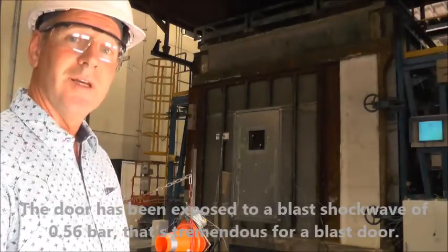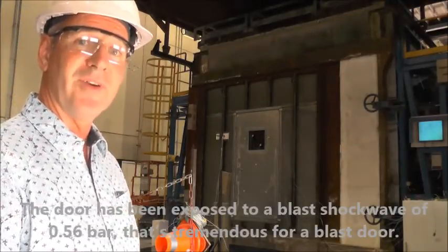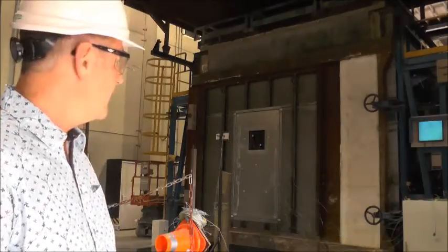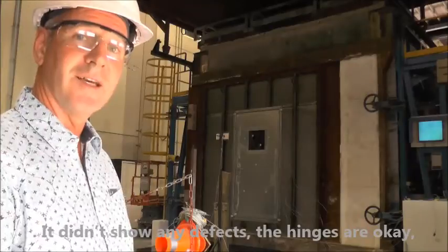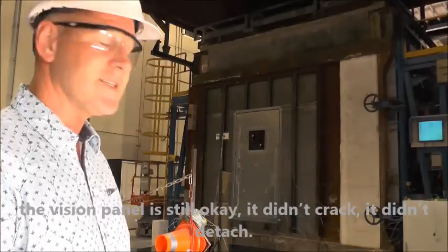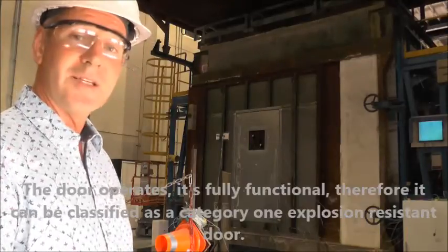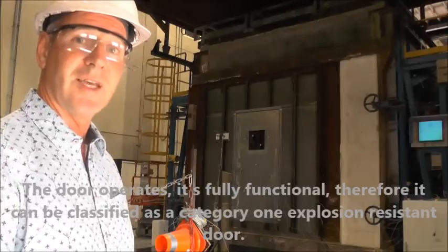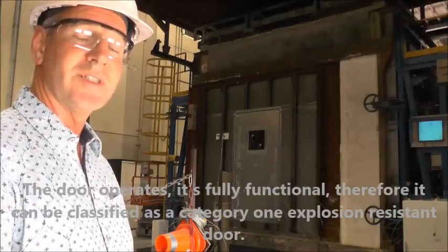The door was exposed to a blast shockwave of 0.56 bar, which is tremendous. It showed no defects — the hinges are intact, the vision panel is still ok, it didn't crack, it didn't detach. The door operates and is fully functional. It can be classified as a Category 1 explosion-resistant door.